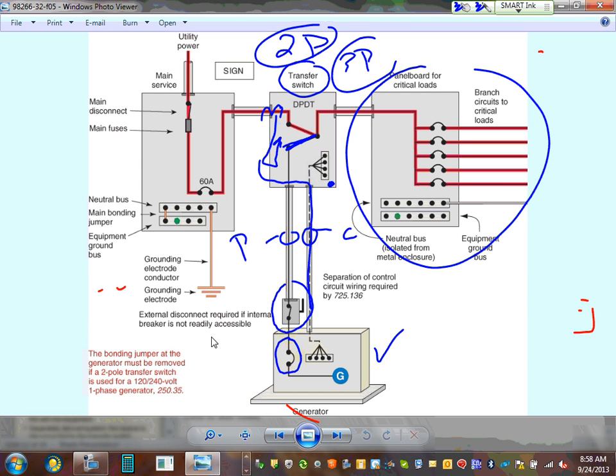Then I want to remind you guys, you continue to feed certain things from this panel. Don't forget that this panel continues to feed other loads. So in reality, inside your house, you have two panels. Both of them are fed from the utility, but when you lose power, one of them is backed up by the generator. Why can't we put the whole panel, the whole service, on the generator, guys?